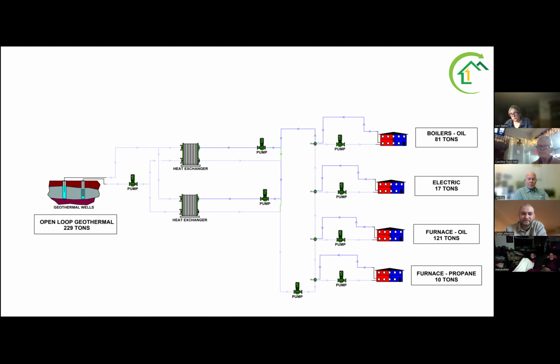Loops in this type of configuration can share energy easily with one another. Whereas the first building and the loop, if it's in cooling mode and giving off heat, then the second building, if it's in heating mode, like shoulder seasons where there might be an imbalance, they can share energy amongst each other where it would not need any of the geothermal to draw from, to reject heat to, or absorb heat from. Setups like this reduce pumping power for a single pump or single pipe configuration. There's lots of benefits for this system type.